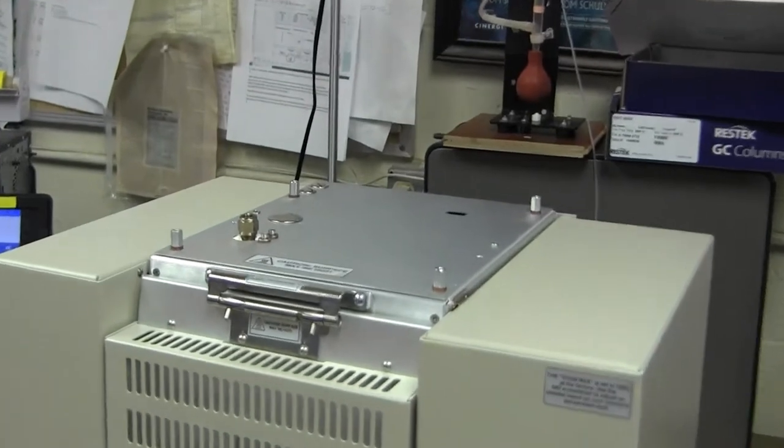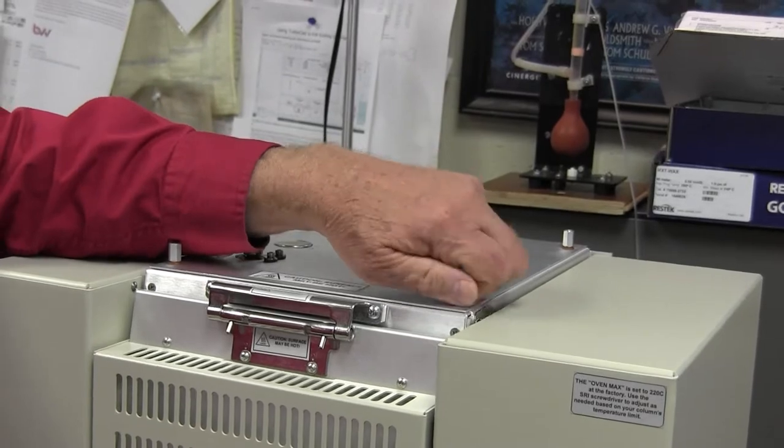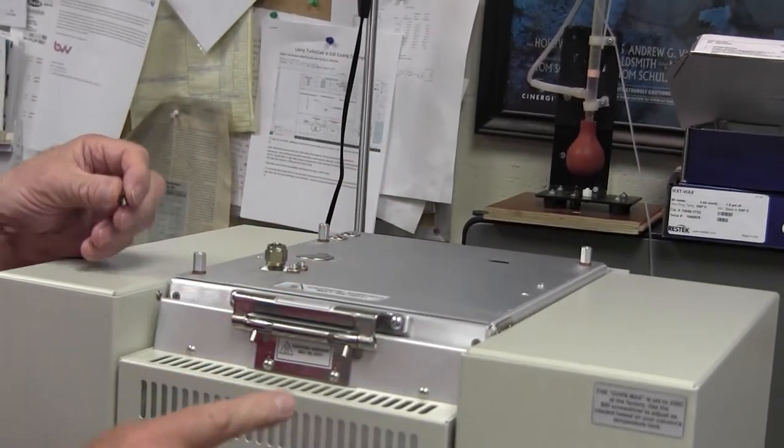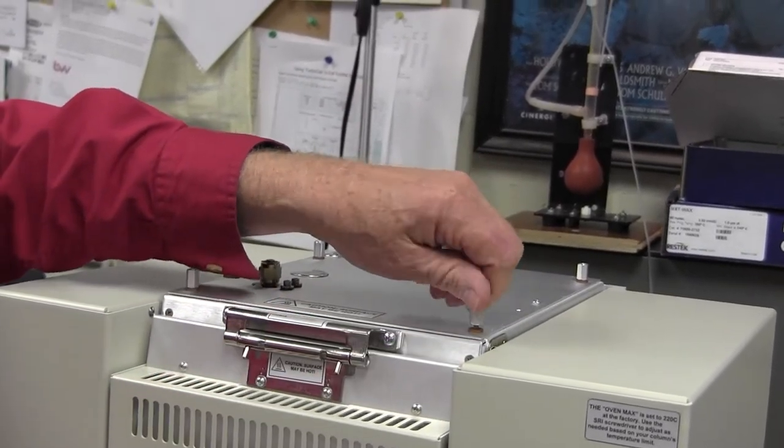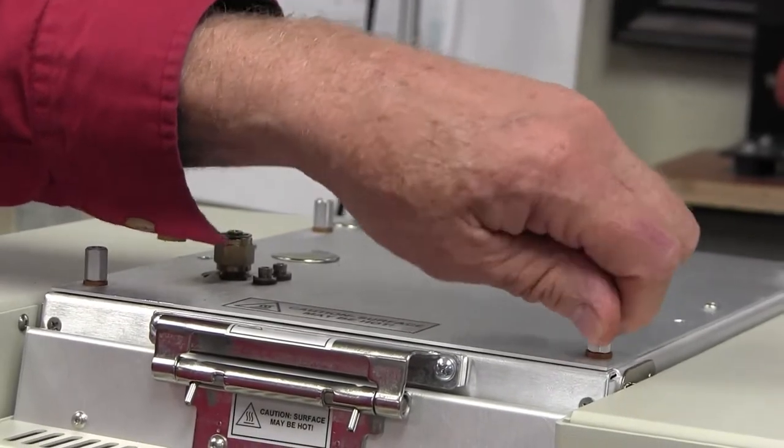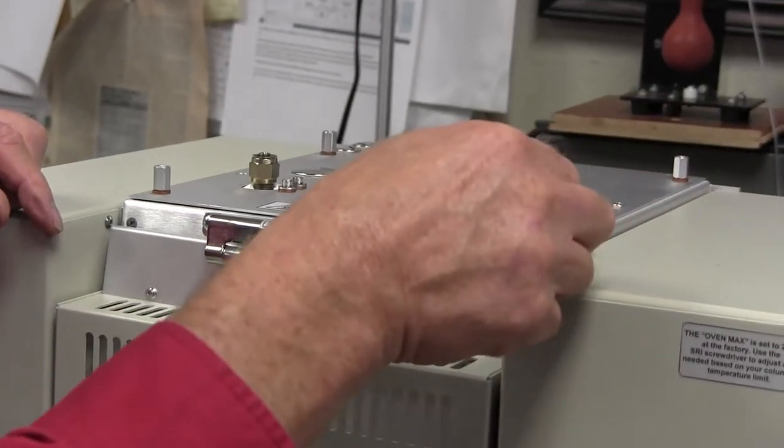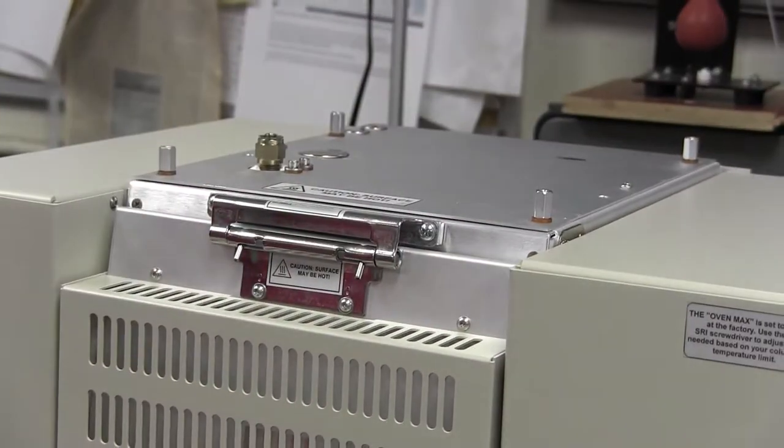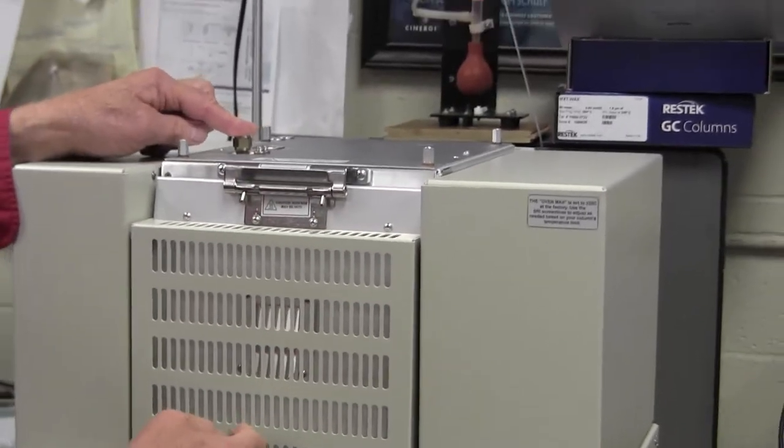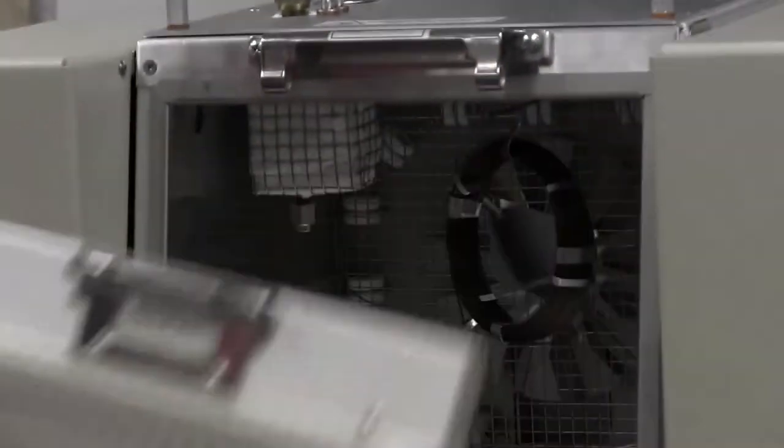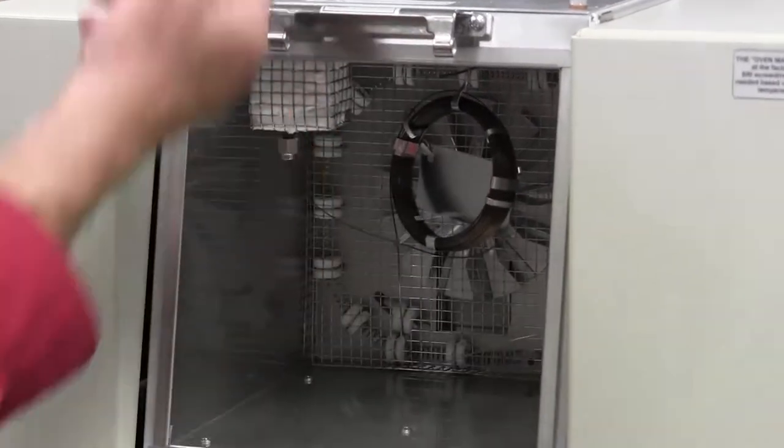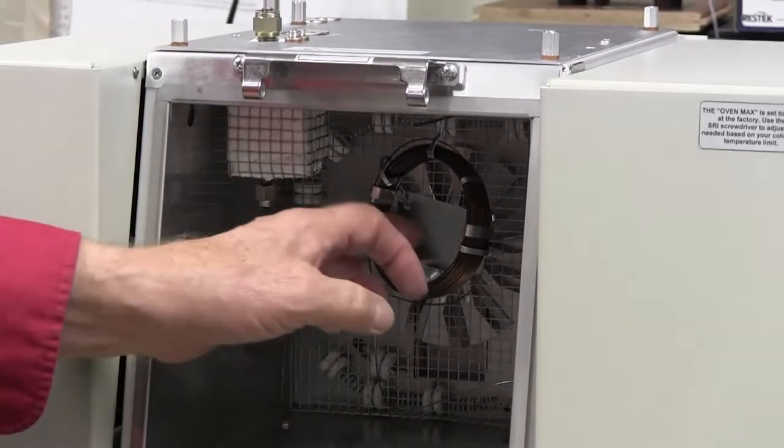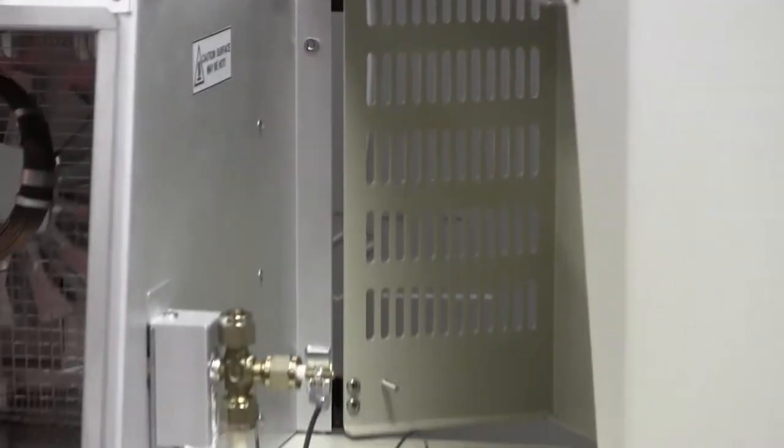So when we ship the GC, these little standoffs are not connected because they would make the shipping a little more prone to damage. So these four little standoffs and brown washers are disconnected when the GC is first delivered. So you'll have to connect these and you use a wrench and they don't have to be super tight but you shouldn't be able to move them with your finger. So this is the injector of the GC. This is the oven of the GC and this is the column that's connected and this is the injection port. In this case it's a heated injection port and the column is a .53 millimeter capillary column and it's going to a flame ionization detector.